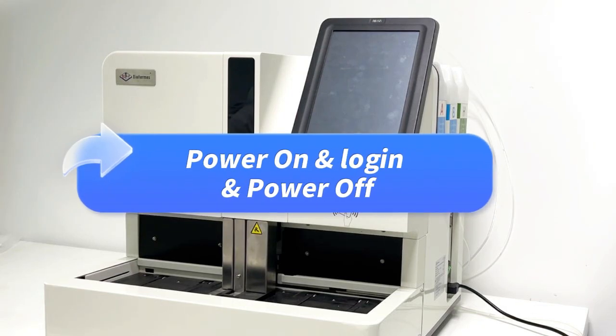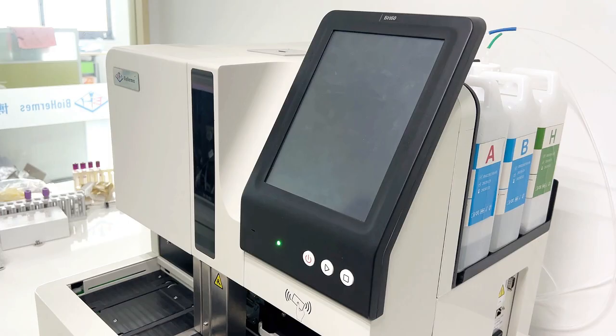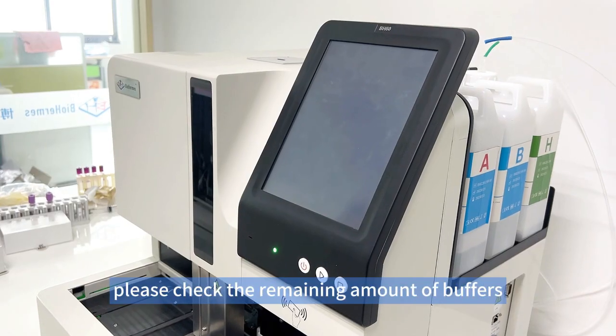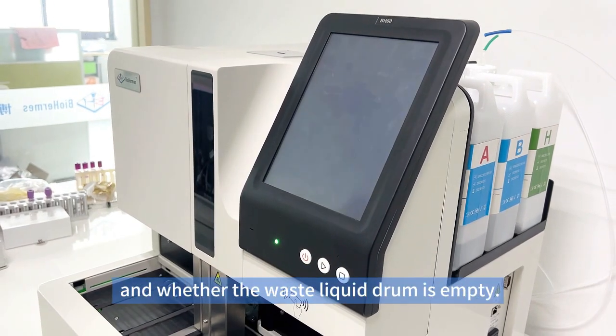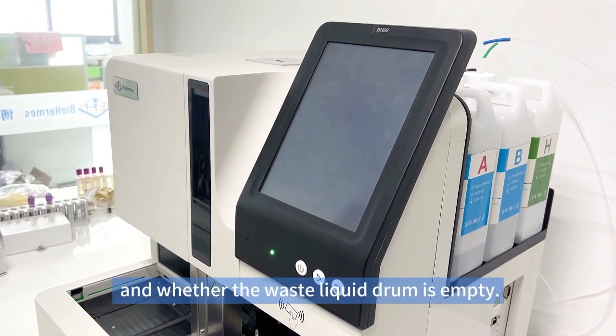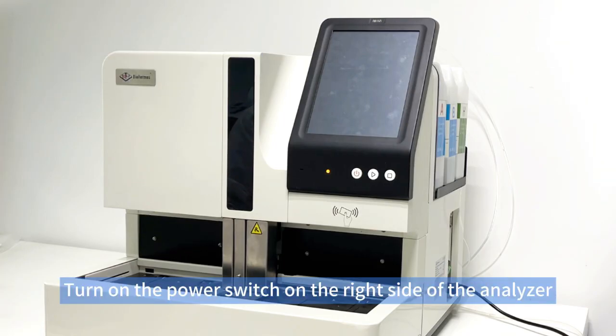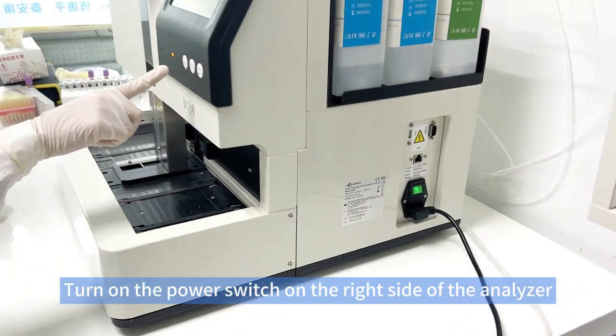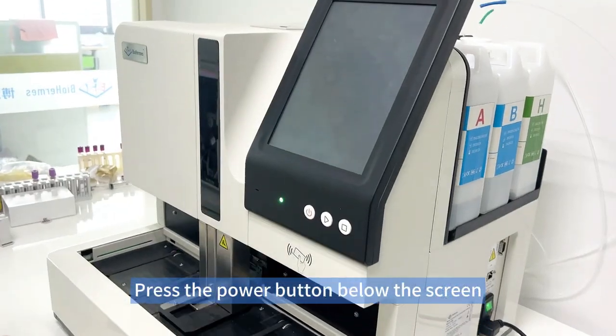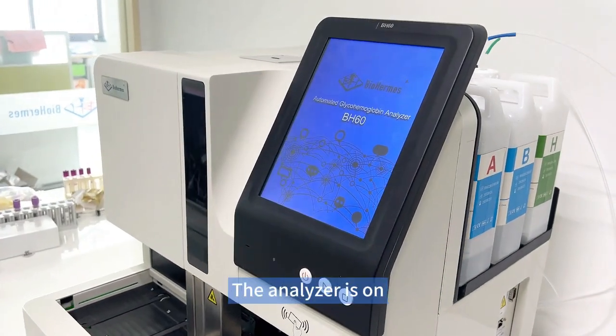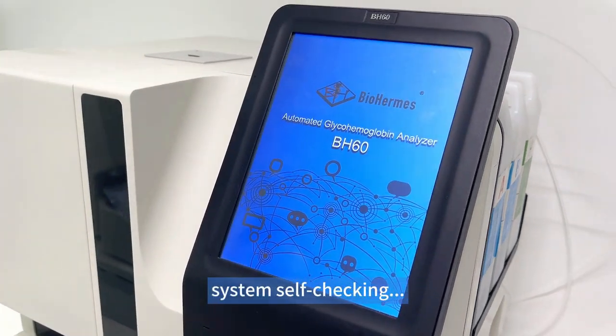Power on. Login. Power off. Before powering on the analyzer, please check the remaining amount of buffers and whether the waste liquid drum is empty. Power on. Turn on the power switch on the right side of the analyzer. Press the power button below the screen. The analyzer is on. System self-checking.